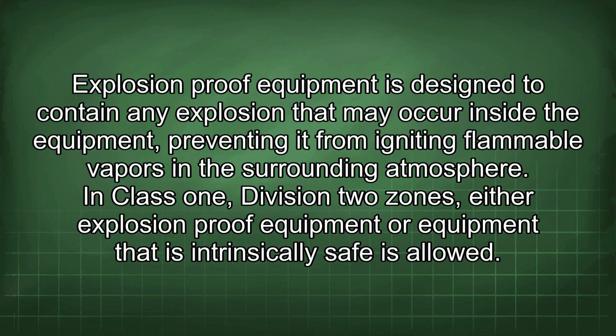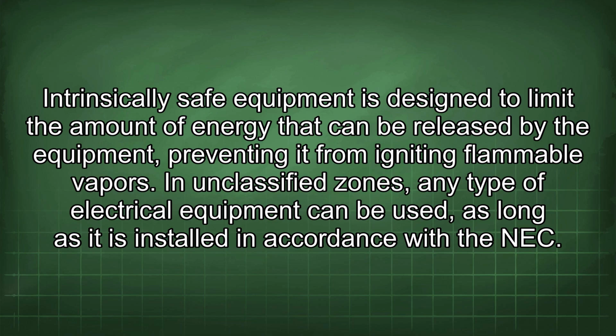Explosion-proof equipment is designed to contain any explosion that may occur inside the equipment, preventing it from igniting flammable vapors in the surrounding atmosphere. In Class 1, Division 2 zones, either explosion-proof equipment or equipment that is intrinsically safe is allowed. Intrinsically safe equipment is designed to limit the amount of energy that can be released by the equipment, preventing it from igniting flammable vapors. In unclassified zones, any type of electrical equipment can be used, as long as it is installed in accordance with the NEC.